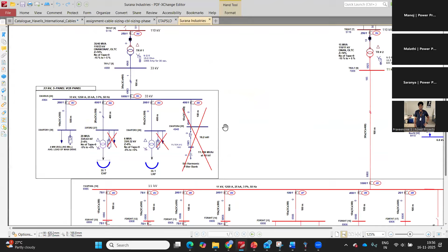So this industry needs what studies? You have loads, you have generation, and you have to perform load flow analysis to find out the voltage profile at all the buses, the losses in each branch, the total losses, the power being imported from the grid, the power factor, the power factor correction needed, and how to set the generator terminal voltage.